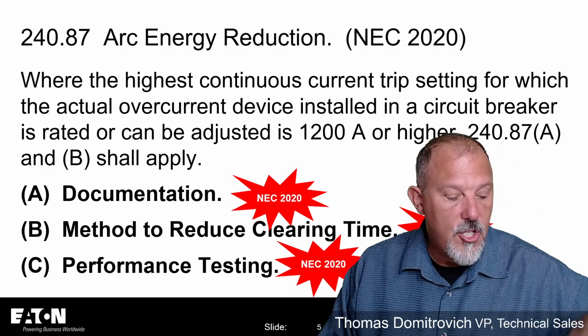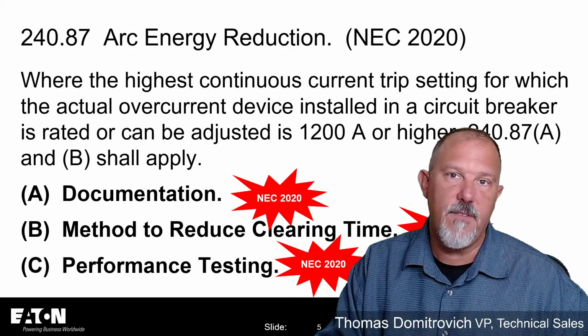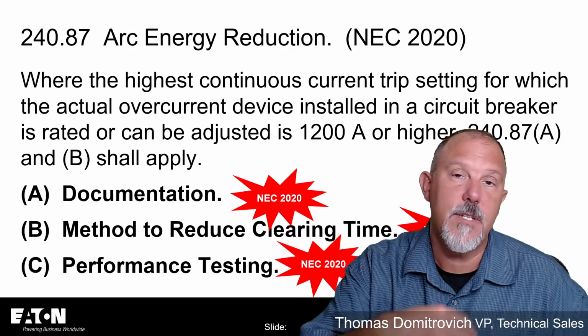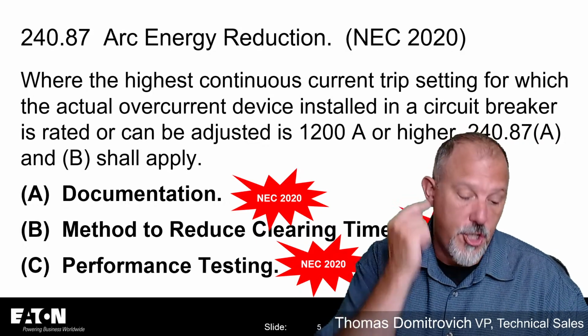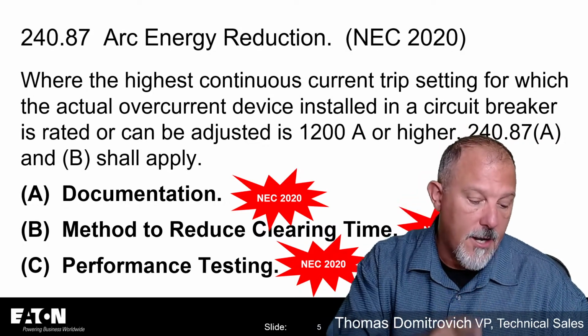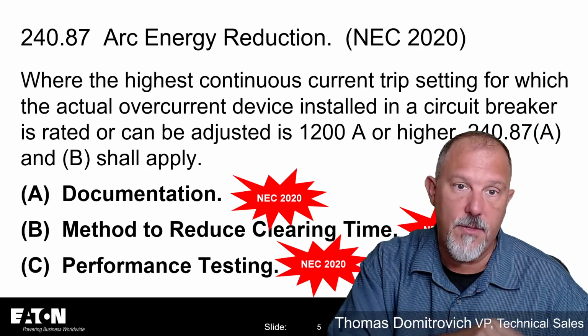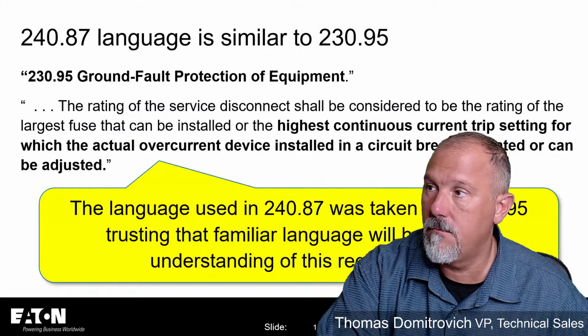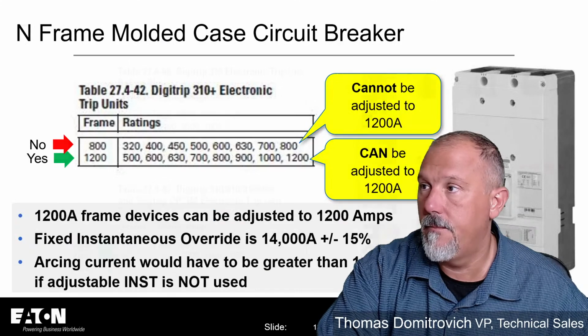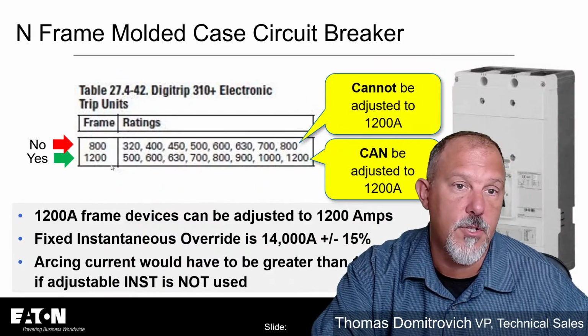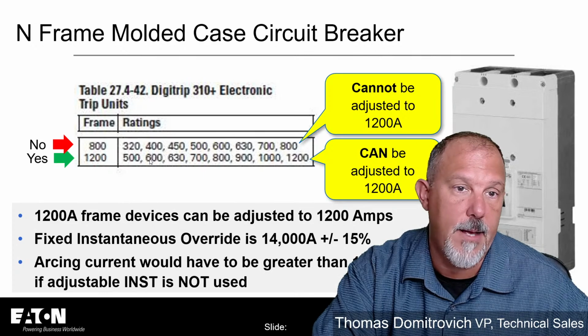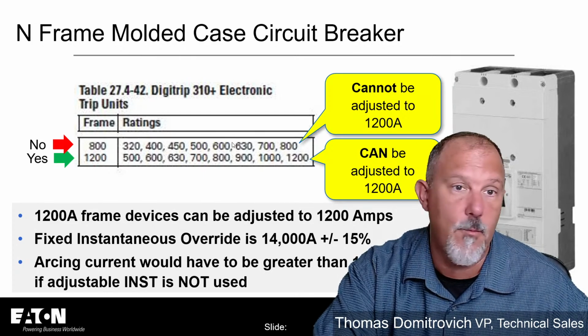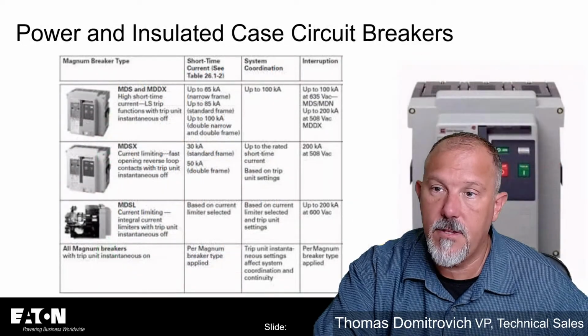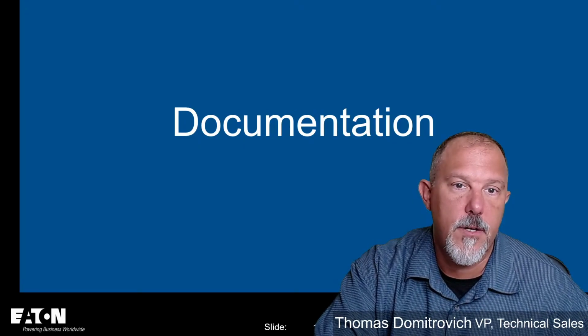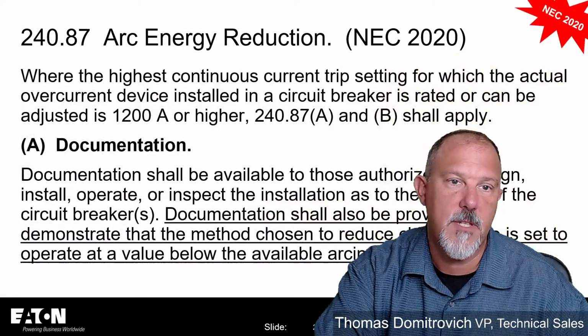Now, the 2020 code added another level of detail. You have to demonstrate, you have to first show on paper in the documentation. Remember, in A, the documentation tells us that we have to, here's a good example. There's a 1,200 amp frame that can be adjusted up to 1,200 amps. That is going to need it, but the 800 amp frame will not. Excellent, James. Let's go to documentation. What does documentation say?